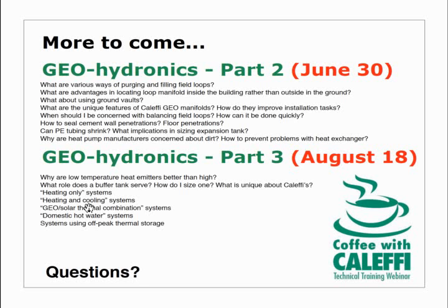Great. Another one, I think you probably covered this a bit. So if you want to keep as much heat in the ground, wouldn't it be better to send the heat to the ground instead of putting it in the domestic water in the cooling mode? The problem there is how much of that heat do you retain? It would be nice to think that all summer long you could dump heat into the earth loop and simply store it in the ground and then pull it back in the fall from the winter.